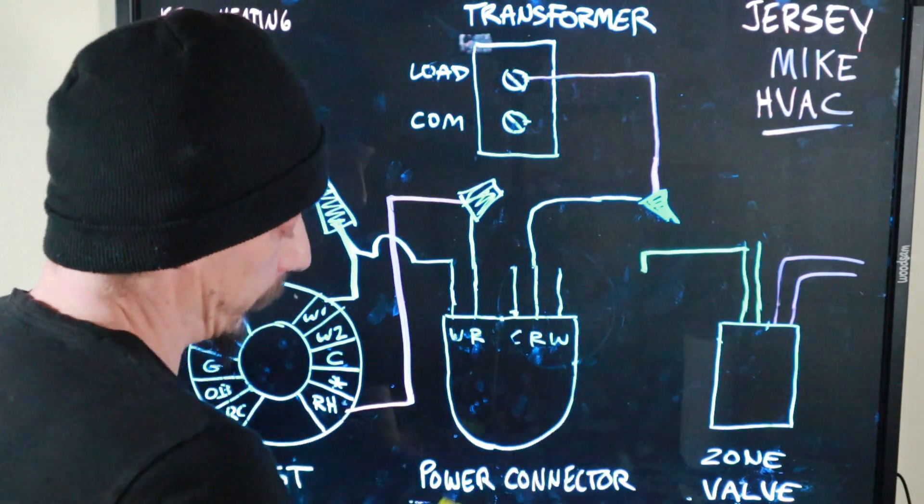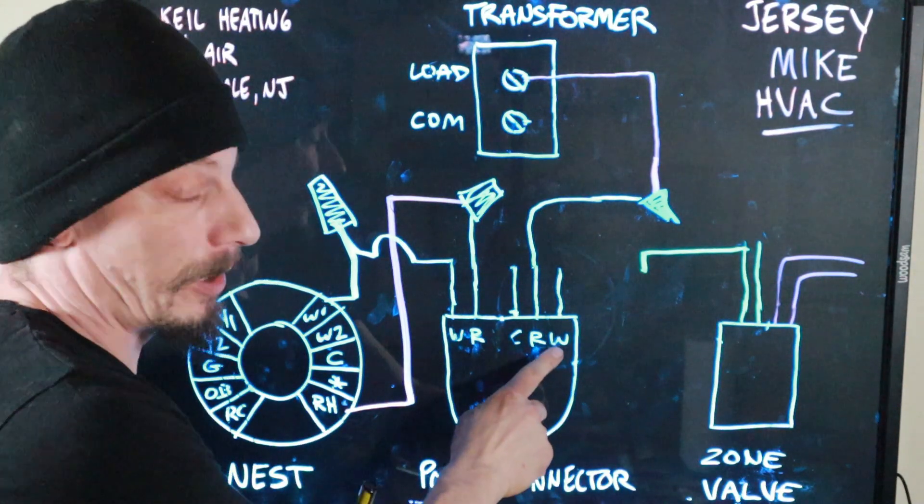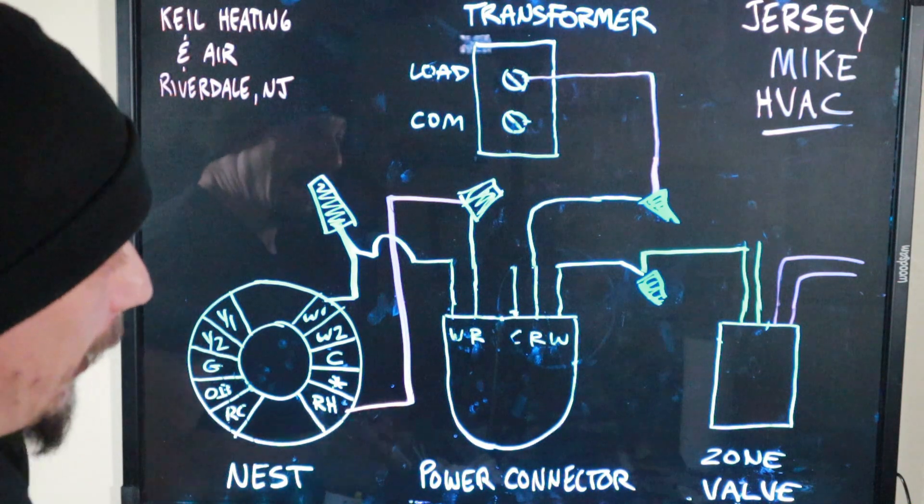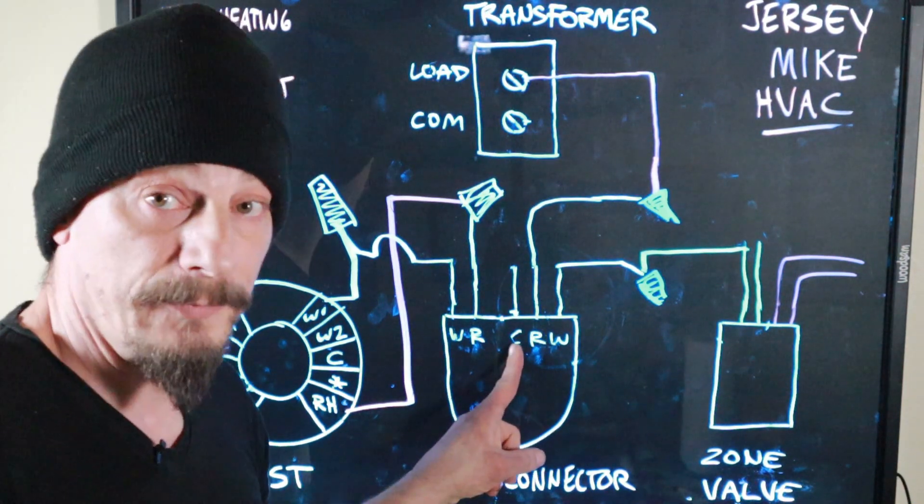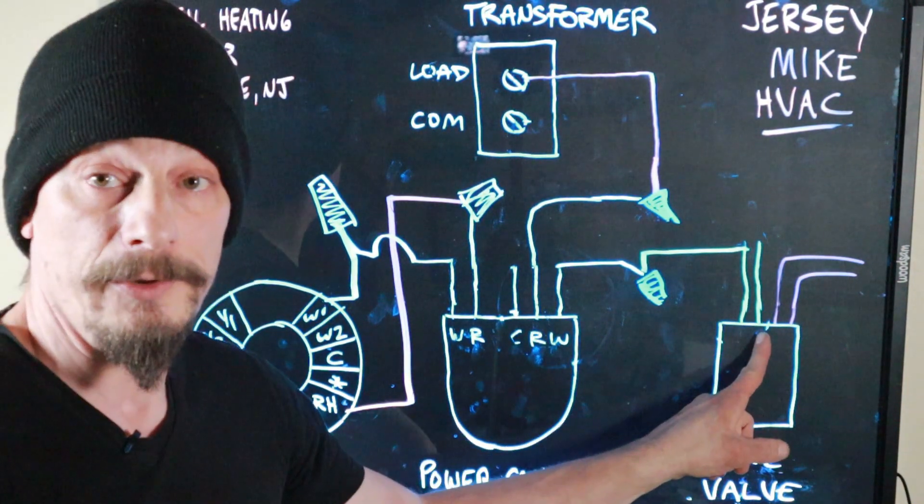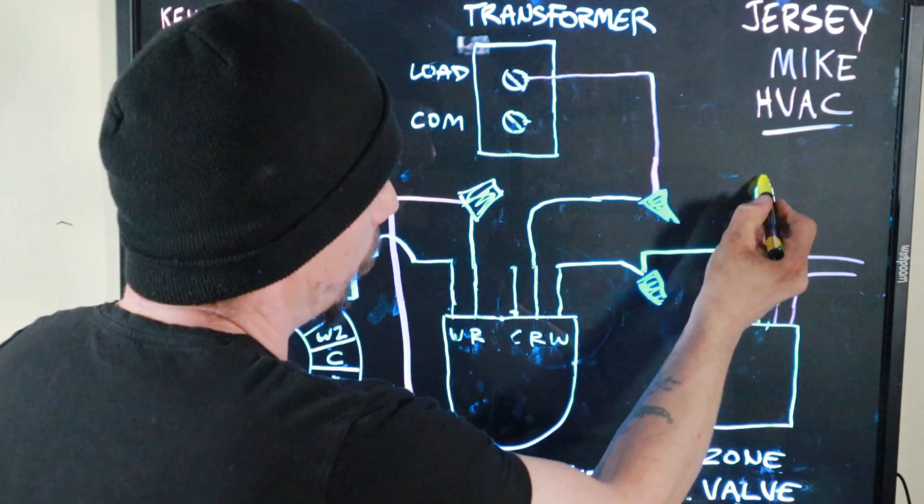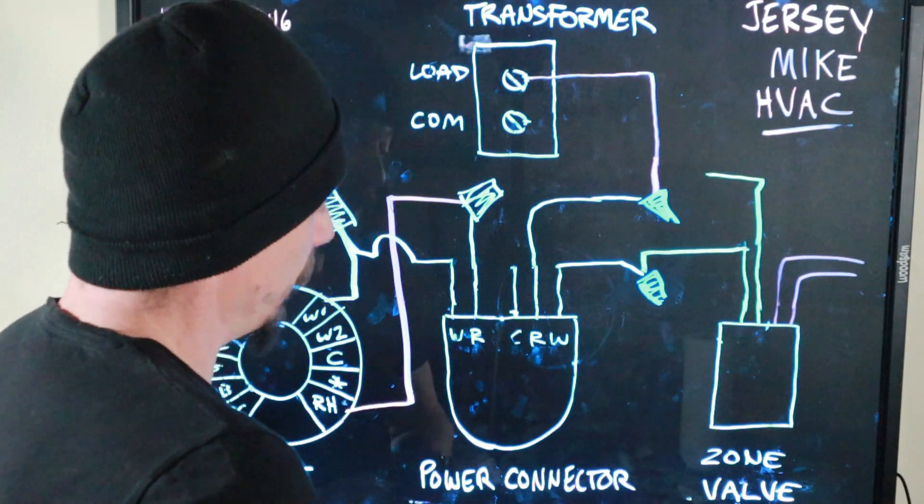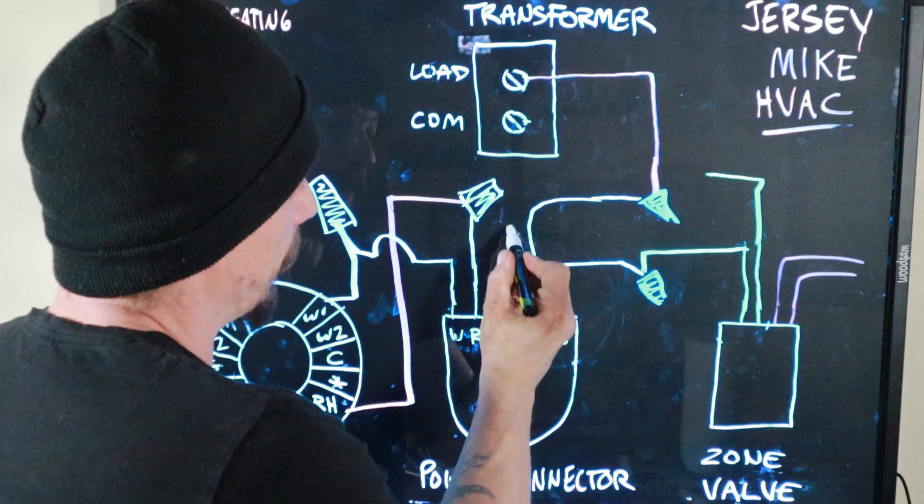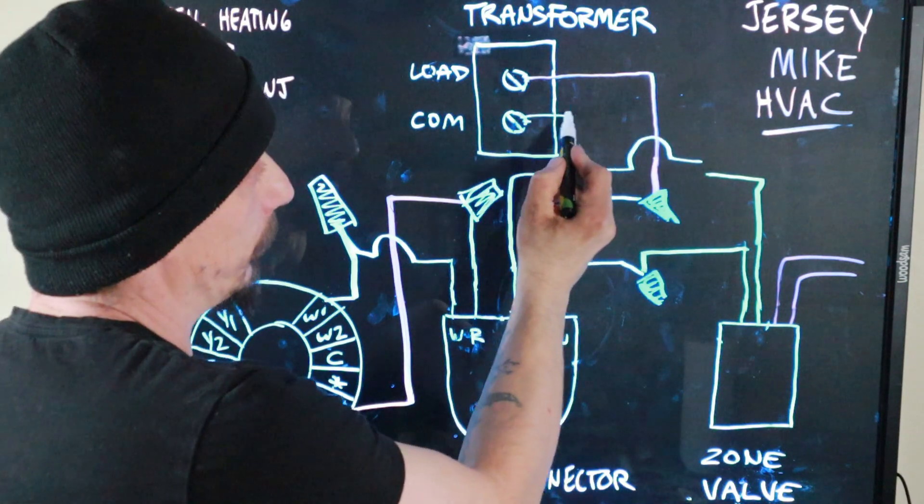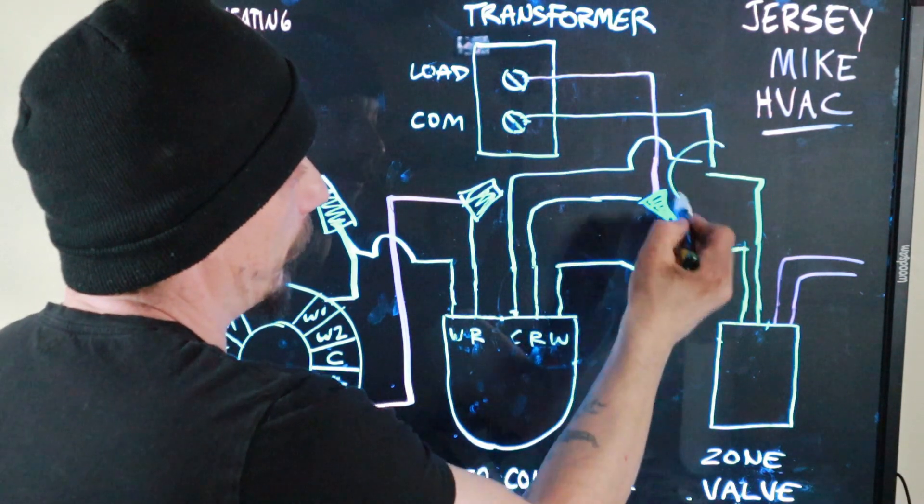So now all you got left is the common wire from your power connector and the other yellow wire on your zone valve. Yellow wire from the zone valve, common wire from the power connector, common wire from the transformer, all coming together right there.